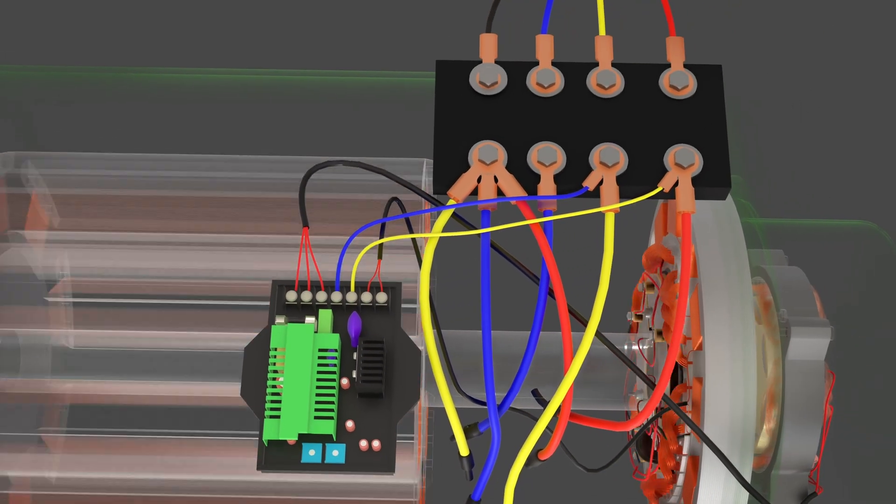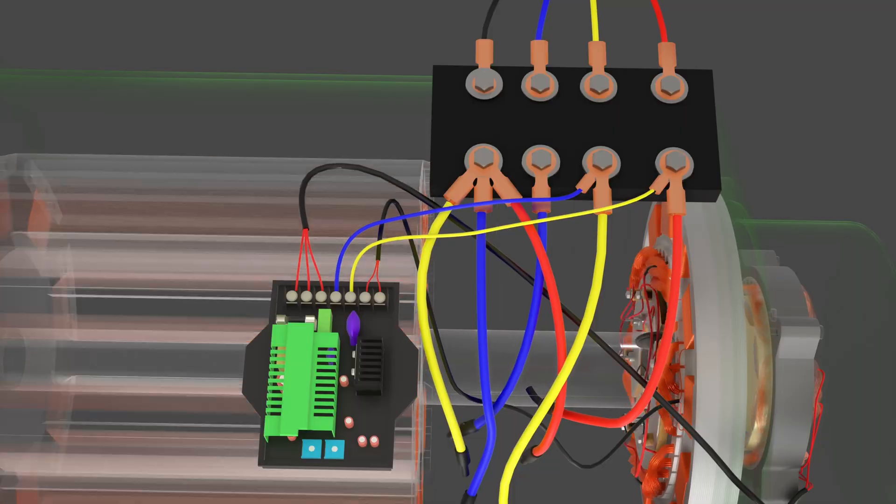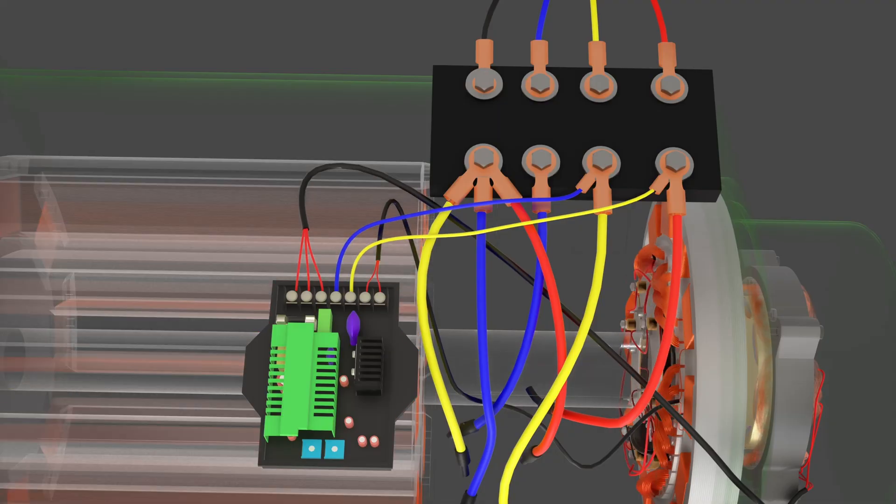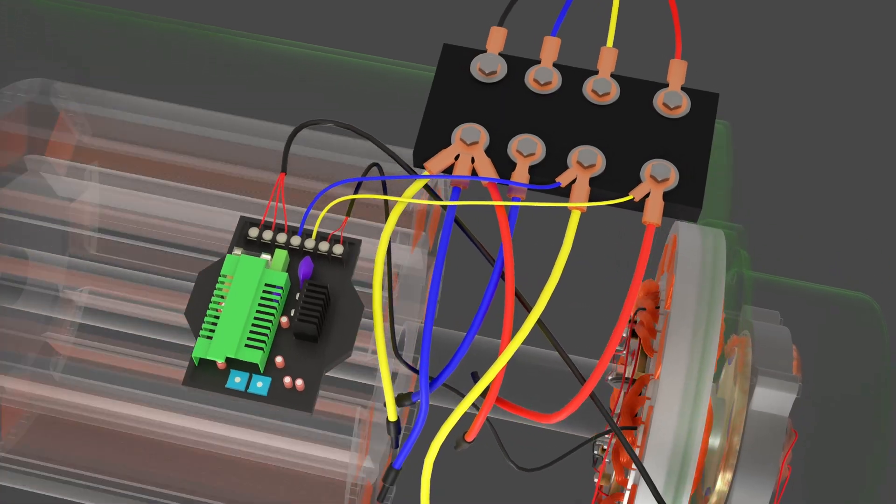When it detects a discrepancy, the AVR adjusts the exciter field current by increasing or decreasing current flow to the exciter stator. This adjustment results in either higher or lower voltage at the main stator terminals, bringing the output back to the desired level.